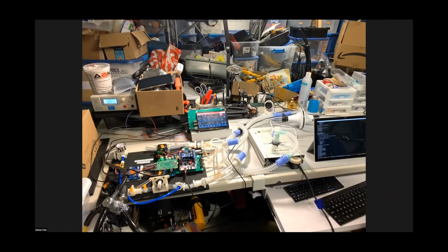And we're going to let it just do a couple of apnea breaths first so that we can see what the baseline looks like. And then we'll do a few triggers. And we'll do triggers at different times in the expiratory phase so that you can see the difference when it's being triggered. And we'll finish off with one more apnea breath.